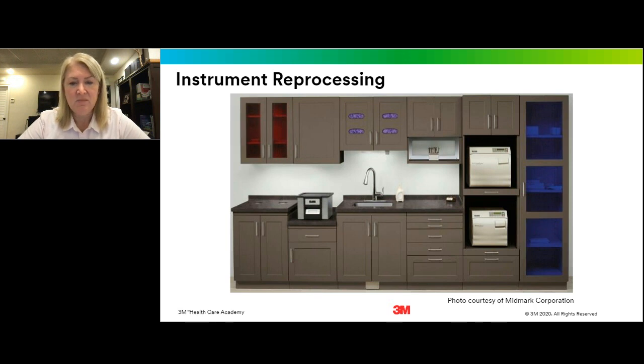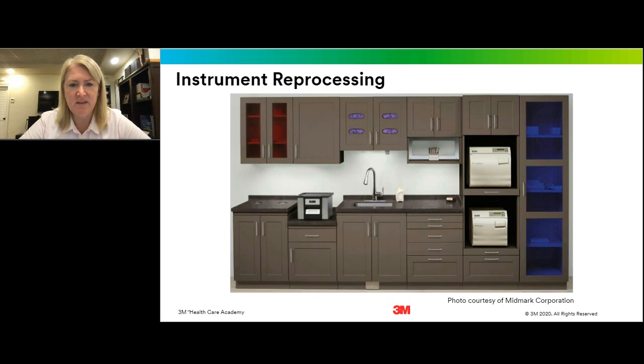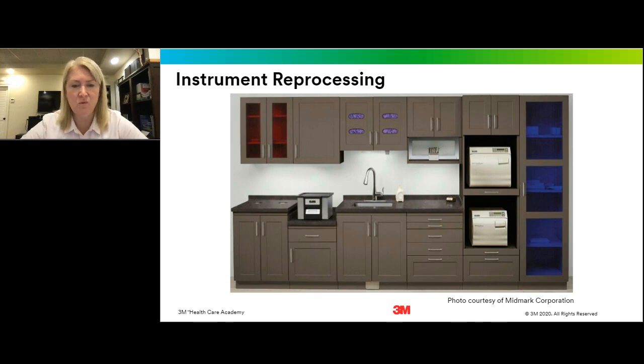There are four key areas in the sterilization workflow. To the left is where we receive, clean, and decontaminate instruments. Next is preparation and packaging. Then sterilization and monitoring at the sterilizers. Finally, storage — represented by the blue cabinet. All of these steps have to be correctly performed every time.